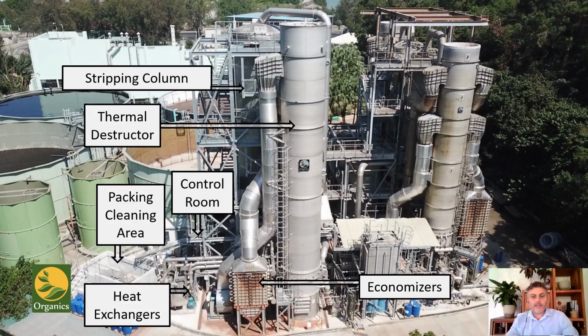The heat recovered in the economiser is sent to the main process heat exchangers, typically a shell and tube wastewater heater and clean water steam generator, seen here to the left of the economiser. Along with our heat recovery heat exchangers, these units provide the system with the necessary hot wastewater and hot air to strip the ammonia in the stripping column.